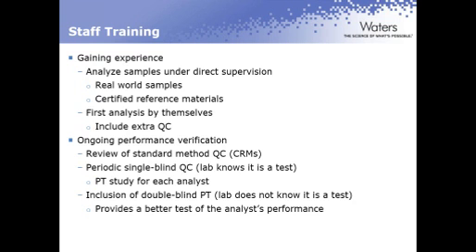So then, after having under direct supervision, let them go off by themselves. Continue to run CRMs, maybe include an extra QC here or there to make sure that they're comfortable and they're competent. Then we go through with the ongoing performance verification. Okay? Review of standard method QC, the results of the CRMs. Here's where the control charting comes into play. Every once in a while, it's really good to do a single blind QC. Okay, what a single blind QC is, the lab knows that it's a test, but they don't know what the concentrations are. Maybe even do a PT study for each individual analyst.